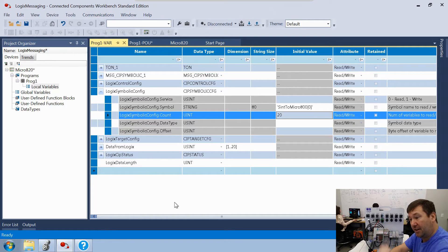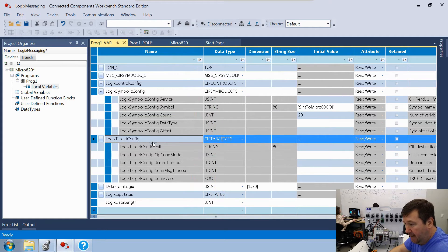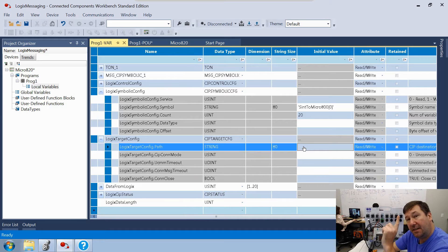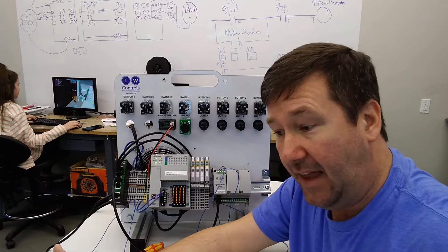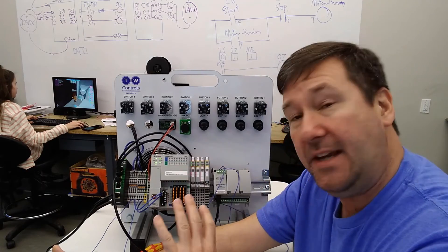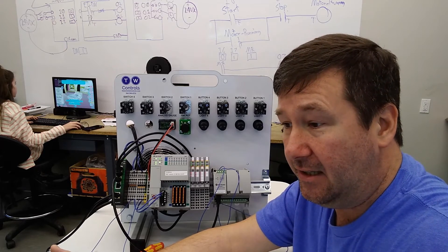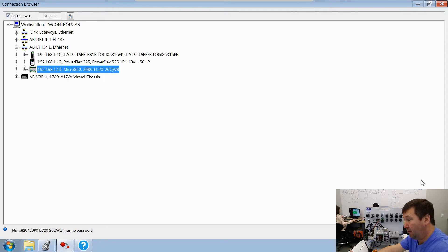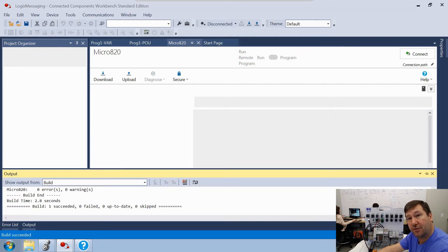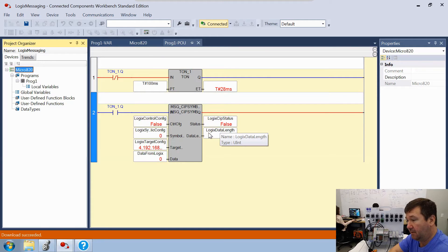We also need to specify the target under 'Logix Target Config.' The main field is the path, which should be the number 4, comma, then the IP address of the PLC: '4,192.168.1.10.' That's all the configuration needed for the basic messaging instruction. Go ahead and download this program. As before, if you need help downloading or configuring drivers, check the description. Switch the controller back to run mode.